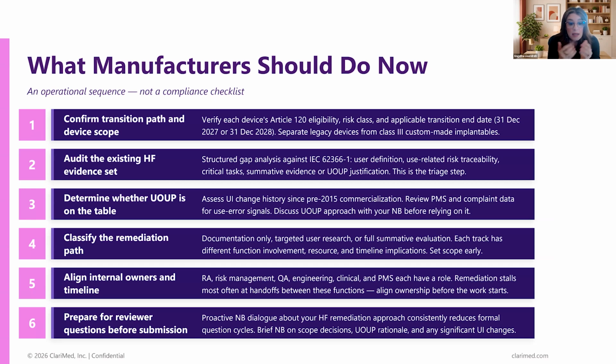And then lastly, come up with a list of reviewer questions that you know that you will have to remediate while the submission's under review. This is a strategy that all regulatory affairs people do all the time. This is not like, oh, we're going in knowing blindly that they're going to ask us. It is a strategy that you have something prepared in the event that it comes in, because as a business, you can start that submission review and go, okay, if they ask this a little bit further, we might have this rationale all ready to go. There's no harm in that.